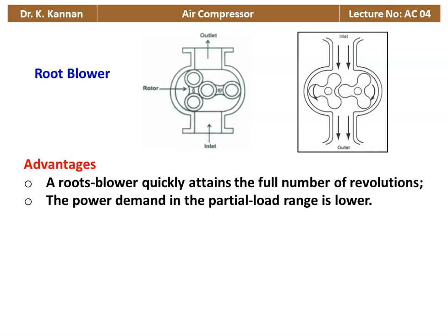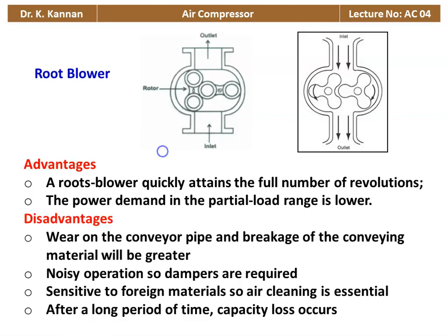The advantages of the root blower: it quickly attains the full number of revolutions, and the power demand in the partial load range is lower. The disadvantages: wear on the conveyor or leakage will be greater because there is contact between solid mechanical surfaces, causing wear on the lobe. Noisy operation — dampers are required. It is sensitive to foreign material, so air cleaning is essential, as dust particles can damage the inner surface of the casing and the outer surface of the rotor. After a long period, capacity loss occurs due to wear and tear.